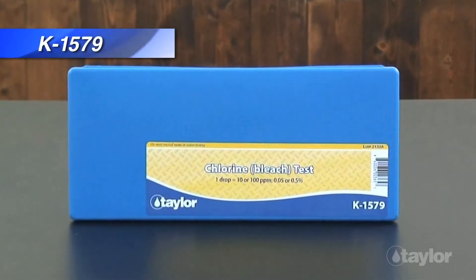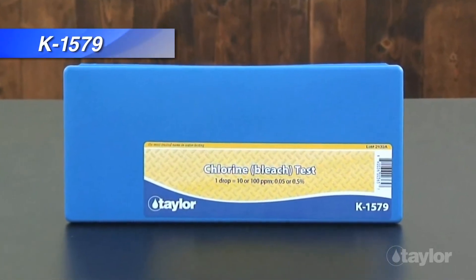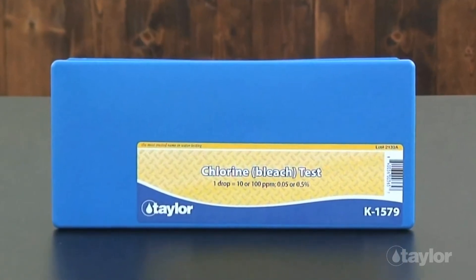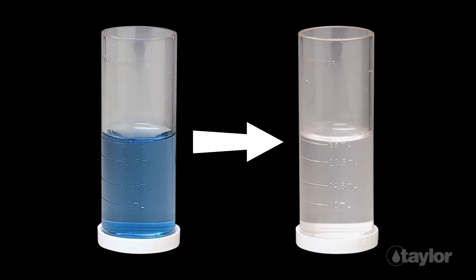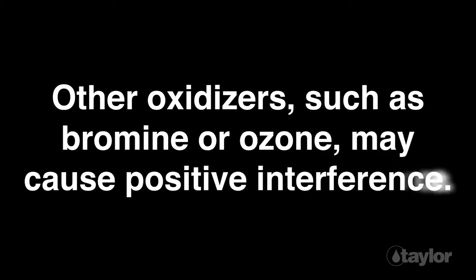The drop test employed in Taylor's K1579 incorporates an iodine starch titration, and the endpoint is easy to recognize as the water sample changes from blue to colorless — no color matching is required. Note that other oxidizers such as bromine or ozone may cause positive interference.